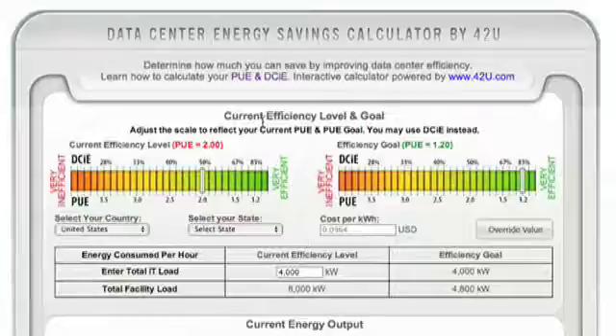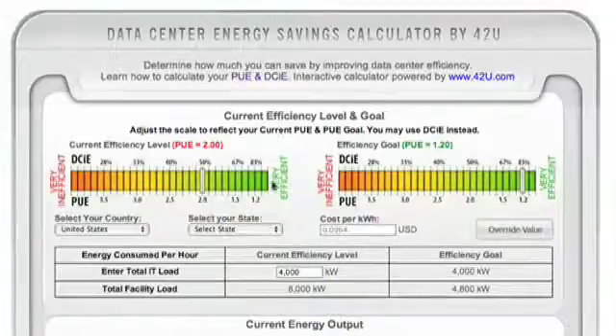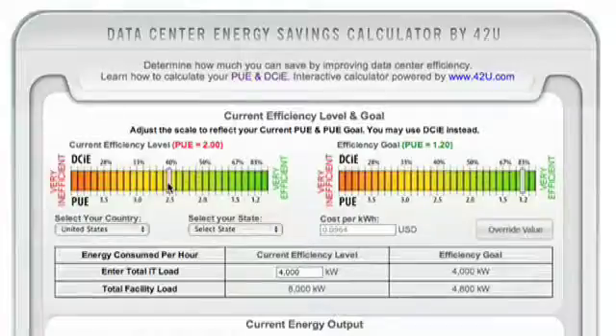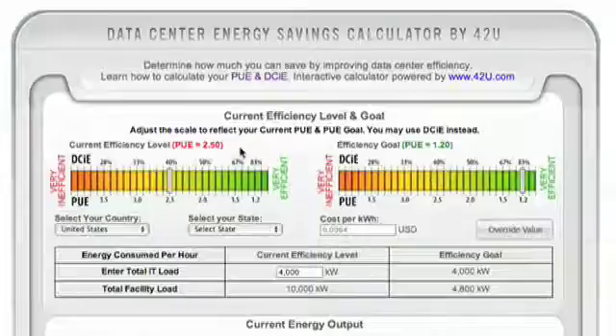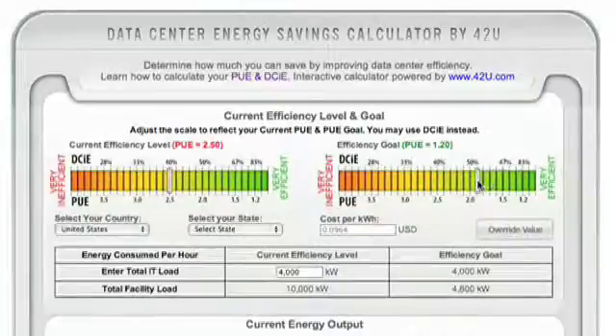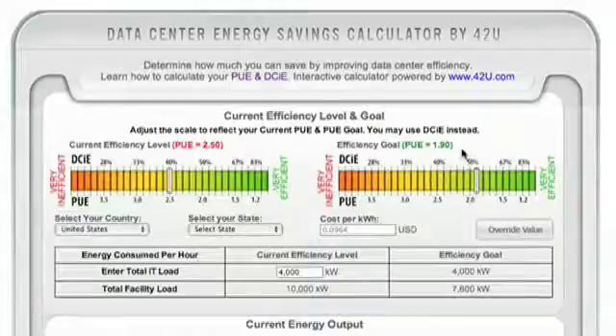In the initial heading, Current Efficiency Level and Goal, our calculator asks for Current PUE and your Goal PUE. If you don't know these values, that's okay. The Uptime Institute approximates an industry average PUE of 2.5. We've seen a number of values between 2 and 3. If you're looking for guidance on how to calculate PUE, you can visit the link at the top of the page. To start the process, let's go with an average PUE of 2.5 — we'll take the slider over to 2.5 and it updates here. And let's say we want to break the 2.0 barrier, so we set the Goal PUE to 1.9. You'll see that updates there.